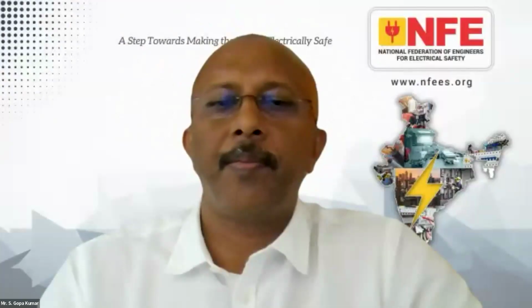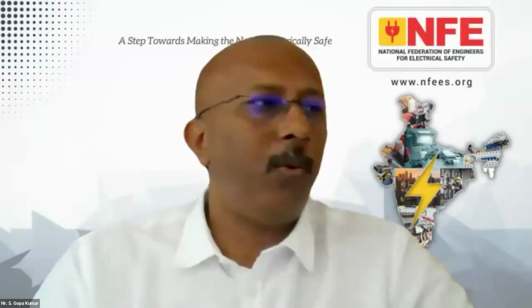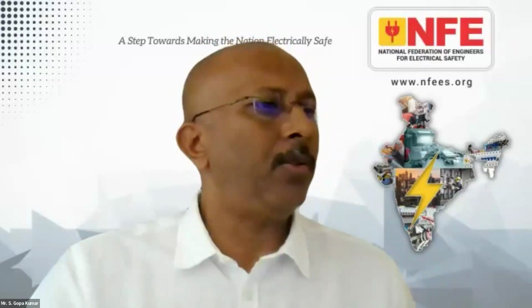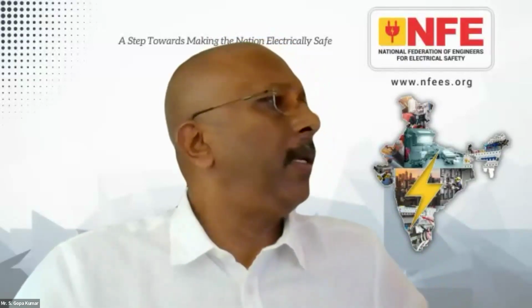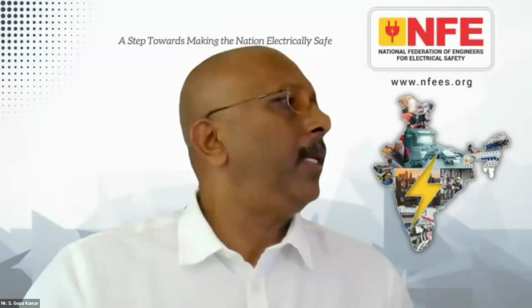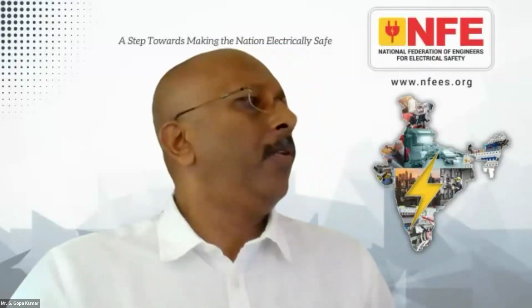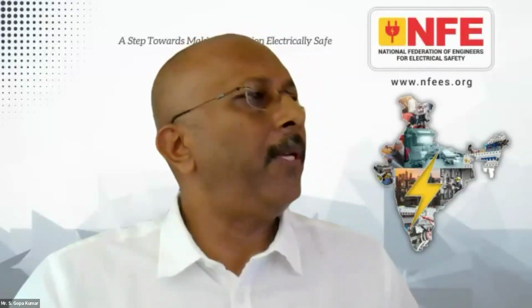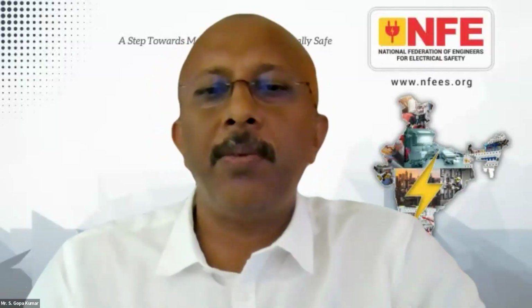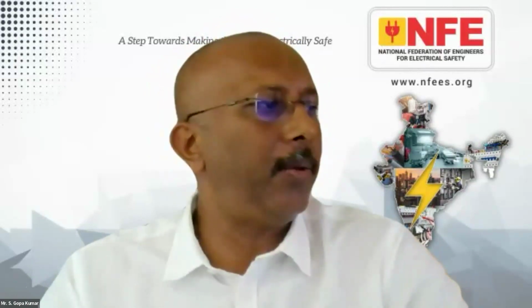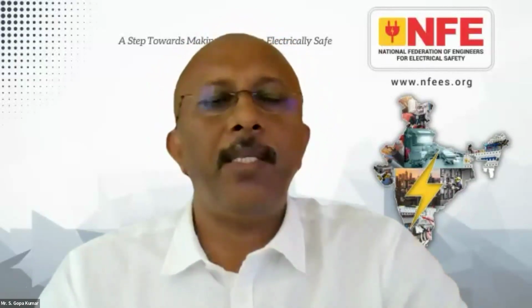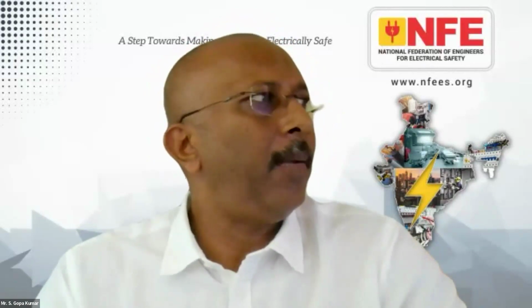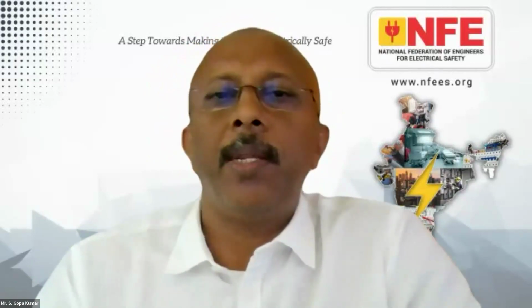For the second question on periodic testing of the medical isolation panel and earthing system in OT — this has to be done, I think once every 12 months or so. Let me read it: functional testing of insulation monitoring devices is every 12 months. Every 12 months we are supposed to carry out this testing. You can refer to page 476 of NEC, clause 9.2, for this.